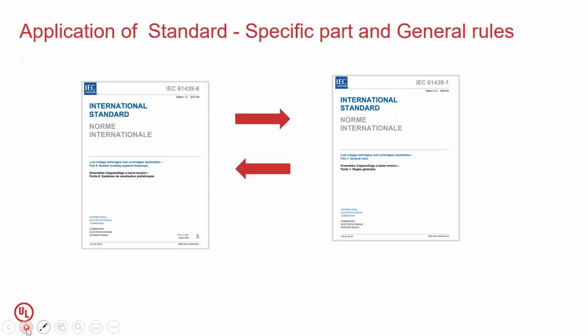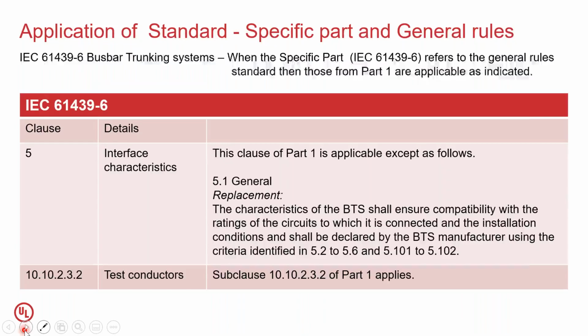Let's now also understand further how to refer back and forth between part 1, that is the general rule standard, and the specific part, which is the busway standard. Many times you're supposed to interact with both these standards, and I will share with you a few examples of how that happens. Now, when should you really go to part 1? You always start with part 6, that is the specific product standard for the bus bar trunking system. When the specific part standard refers to the general rule standard, only then you are supposed to apply those requirements. Let me give you a few examples. If you go through 61439-6, clause 5 is interface characteristics, and it states that this clause of part 1 is applicable except as follows, which means you will have to go to part 1, apply it in totality, and then also make this replacement.